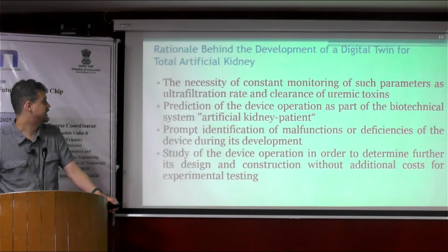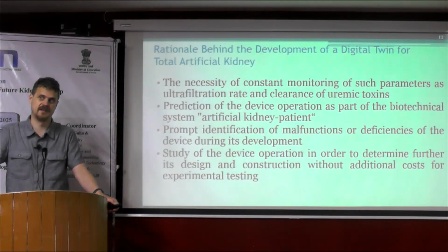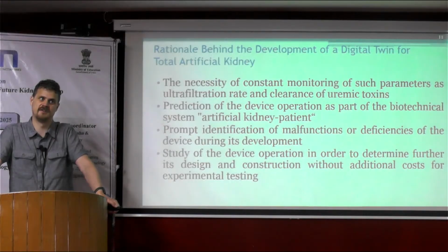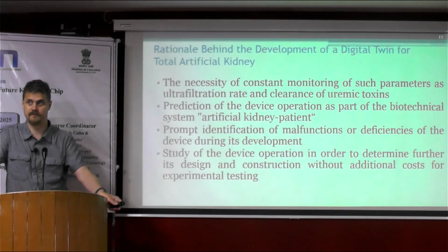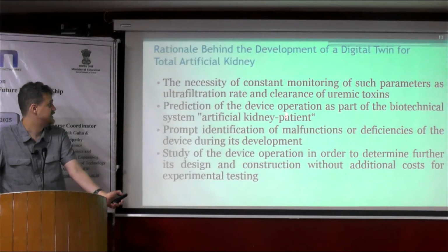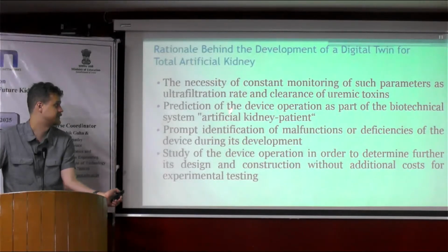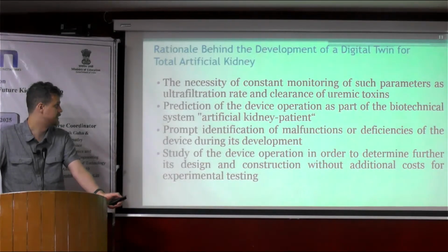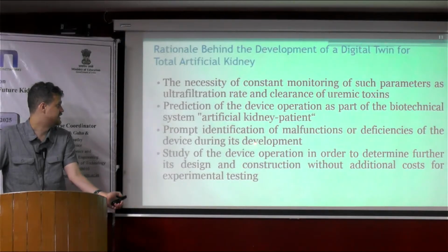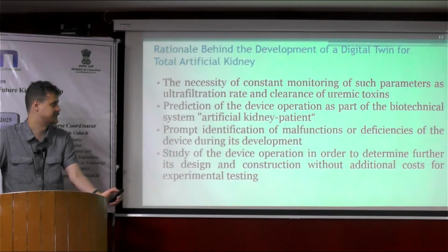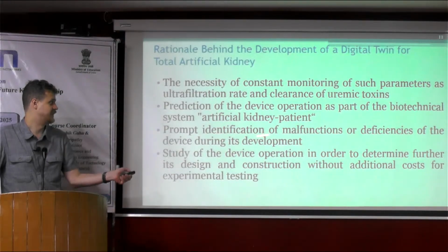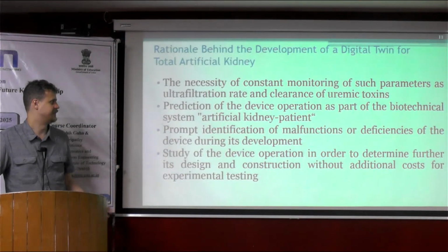In the case of the implantable artificial kidney, since it's an implantable technology and there is no way we can interact with this object once it's implanted in the biological object, we need a means of constant monitoring of parameters such as the ultrafiltration rate and the clearance of uremic toxins. We need to predict how this device will operate as part of a biotechnical system, that is, the artificial kidney-patient system.